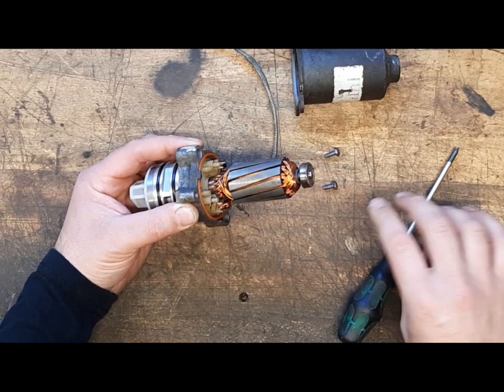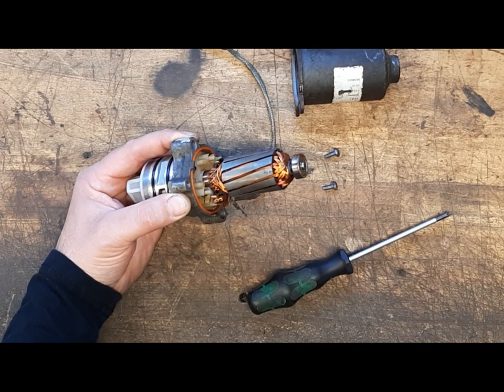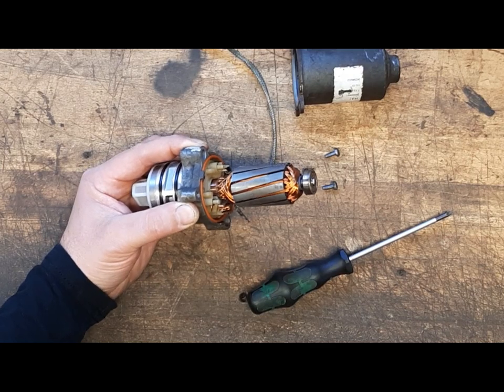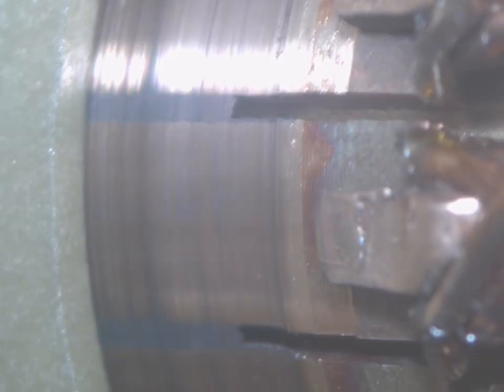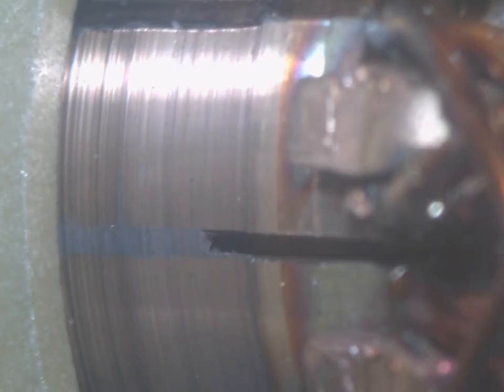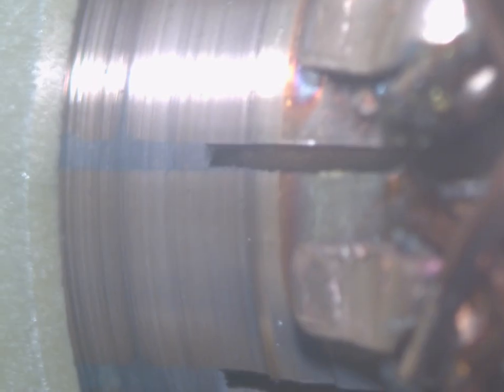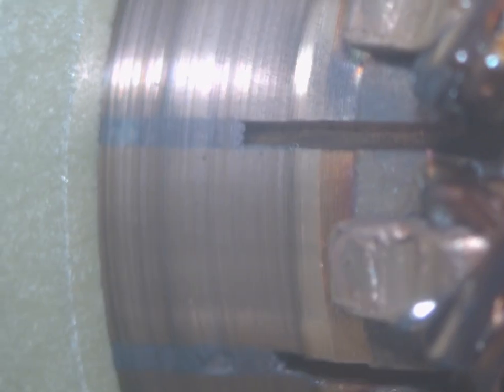I'll get you a nice zoomed in microscope video in a minute so you can see, but these commutator segments wear down and the copper gets knurled over and bridges the gaps between them, so each segment is attached to each other. That basically makes the power that's supposed to be going between the segments, through the field and back out the other side, jump around and go through the segments instead, because each one is touching the other as the copper joins the little stripes together.